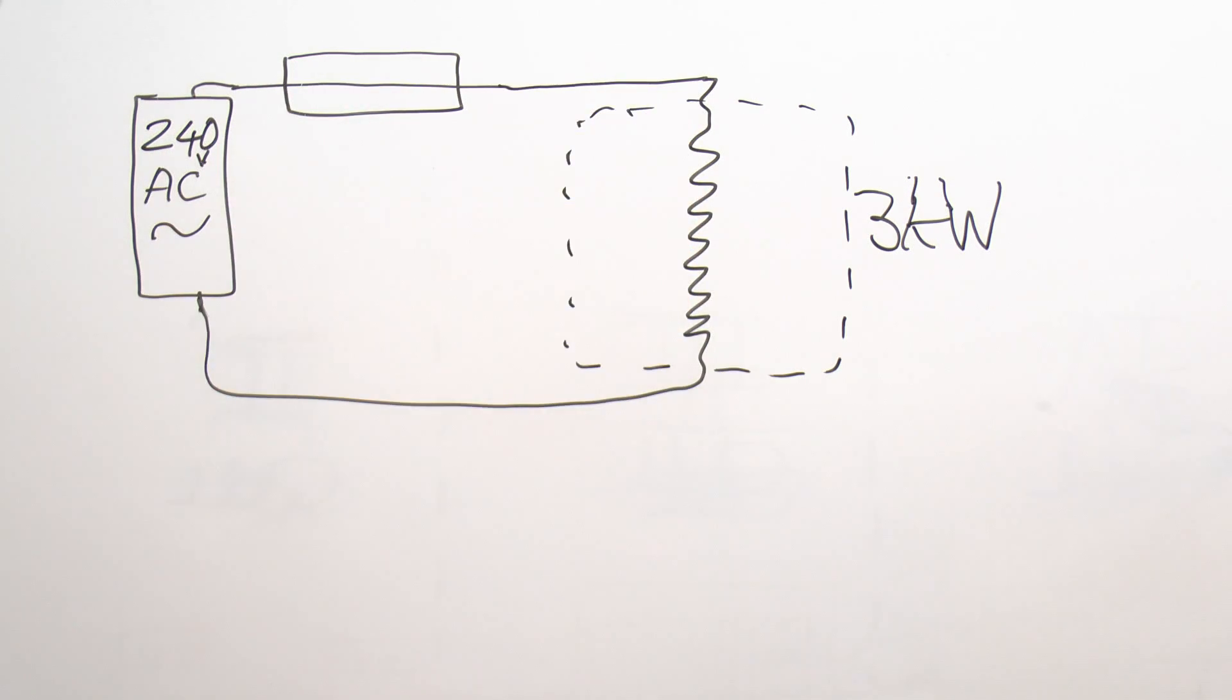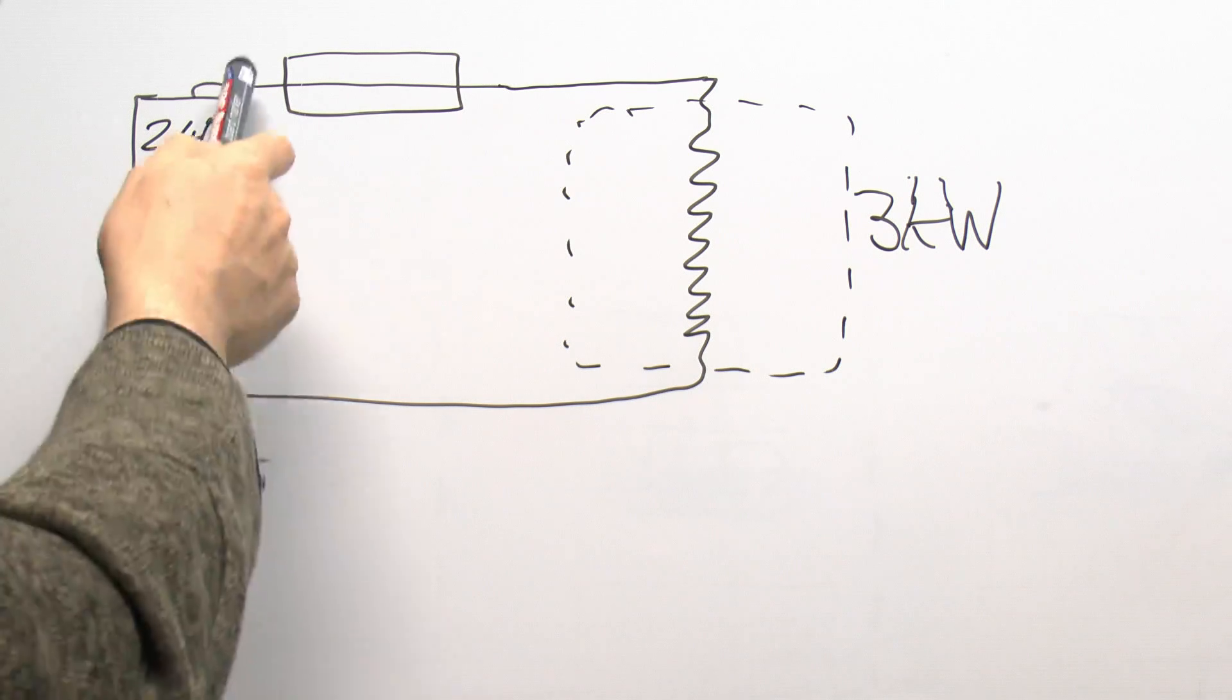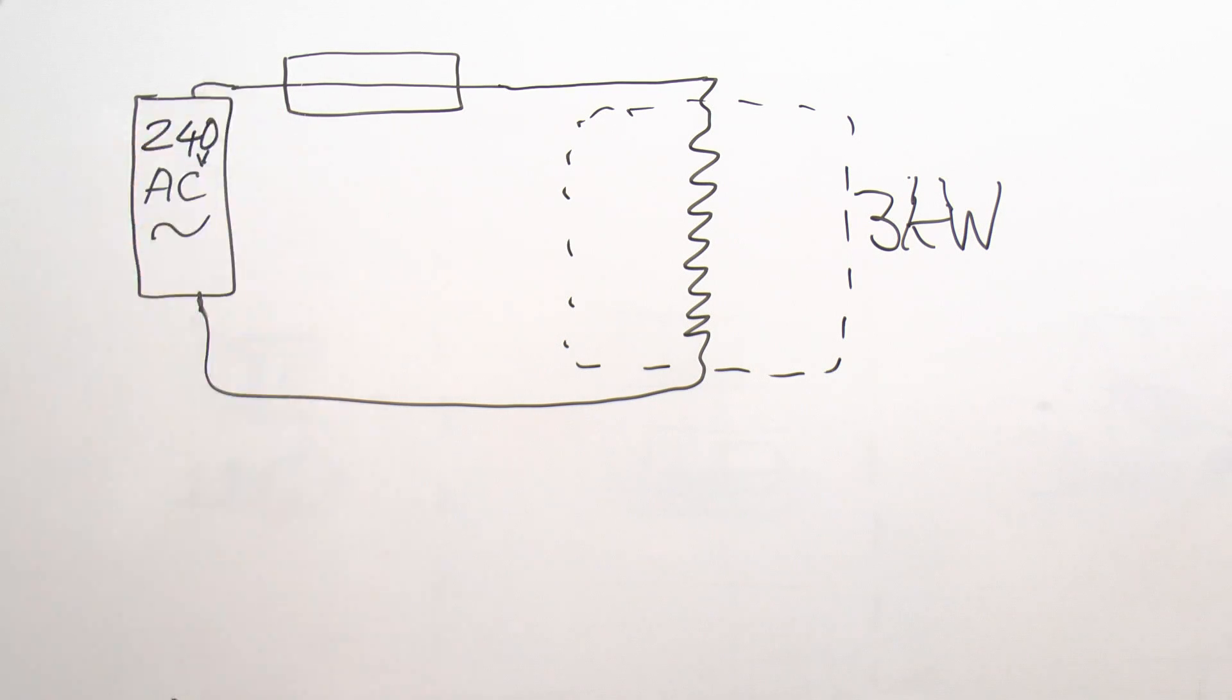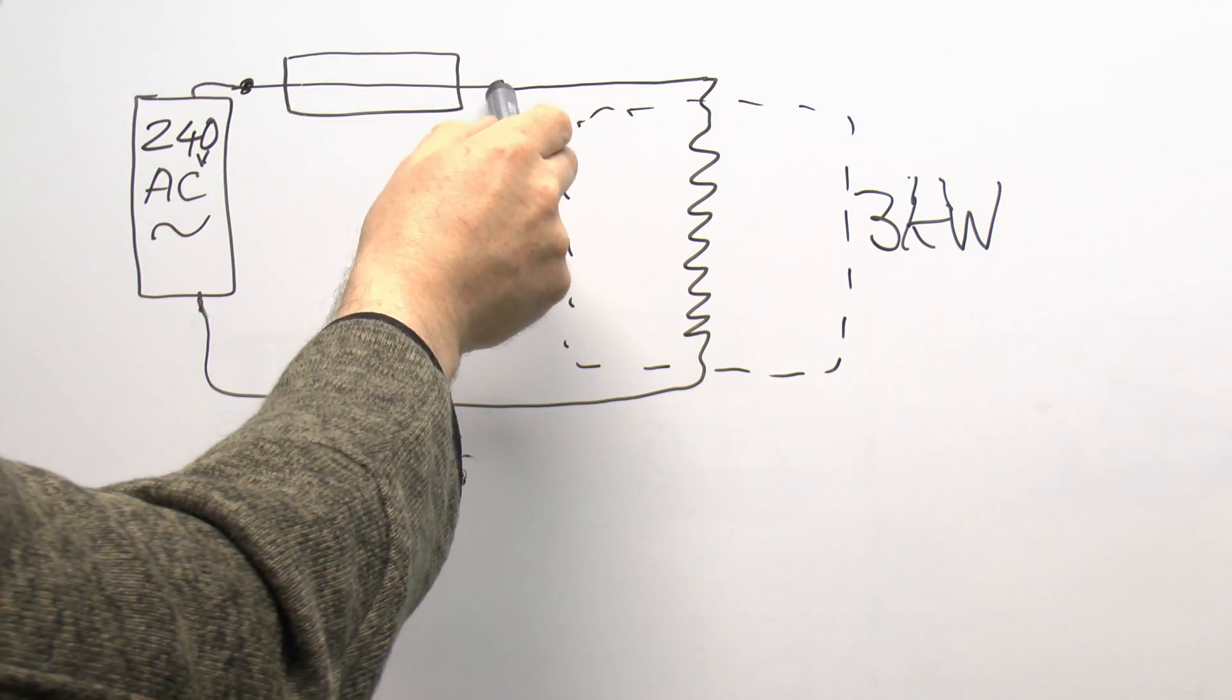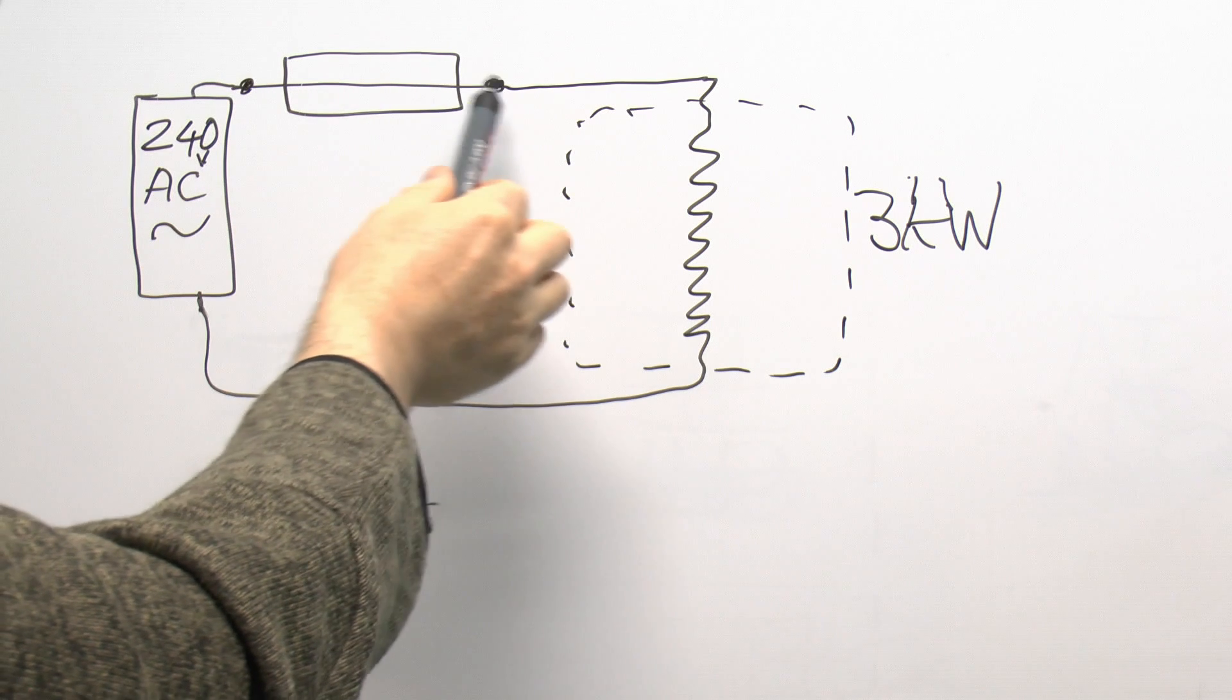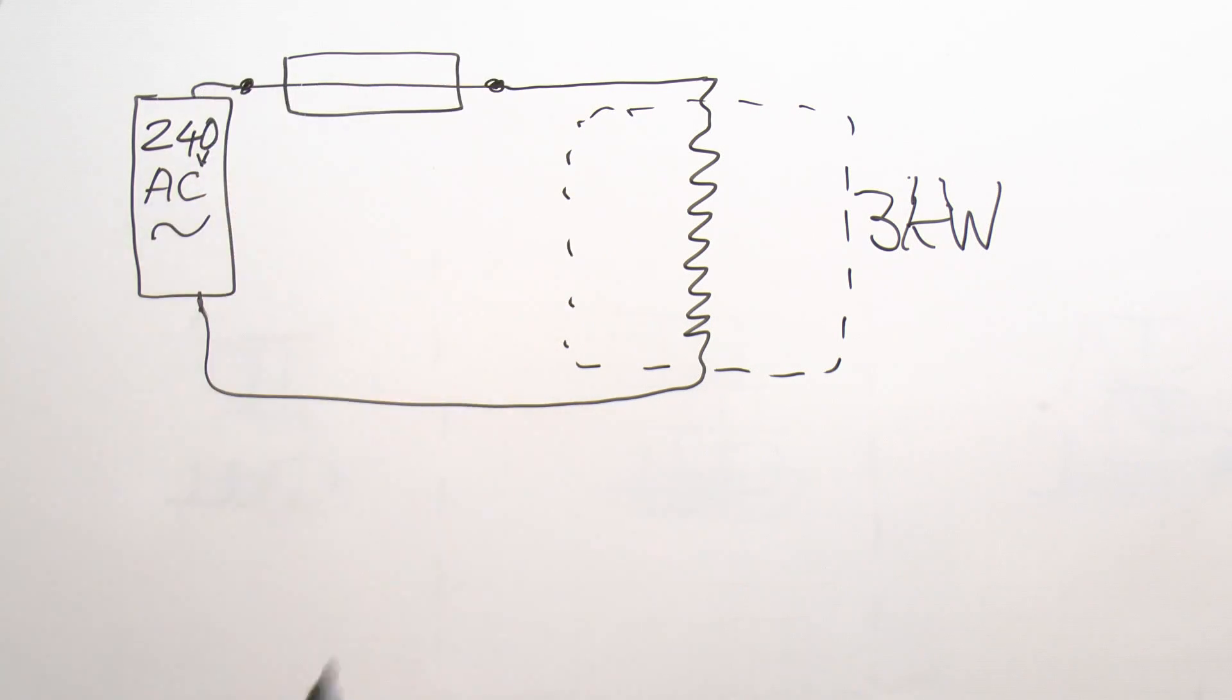Although obviously most of the energy would be wasted in the electric heater over there, and although you've got 240 volts between these two points, you don't have 240 volts between here and here. In this circumstance the voltage here is going to be extremely small, only in the order of one volt or less.